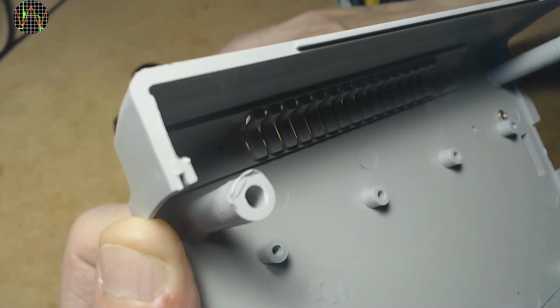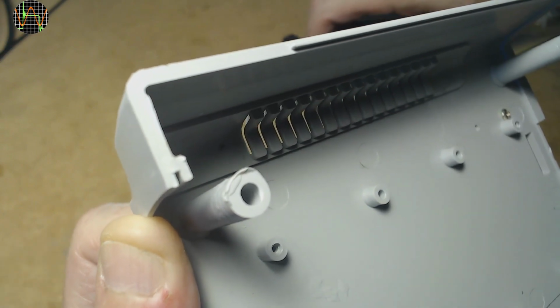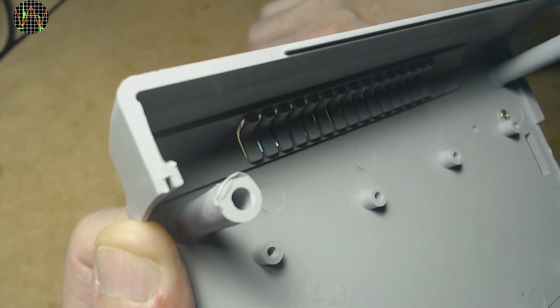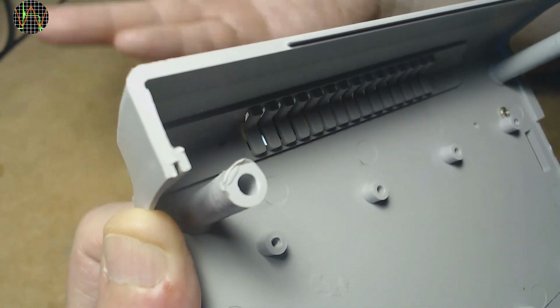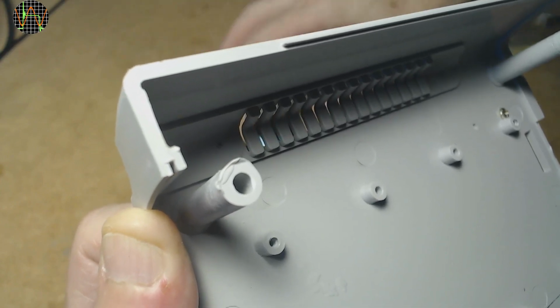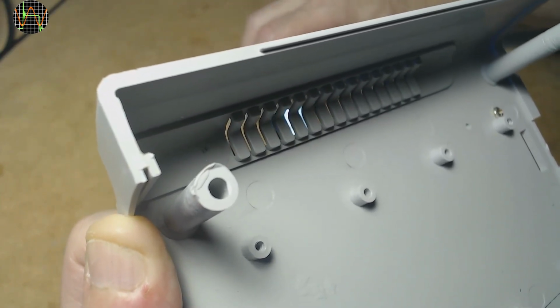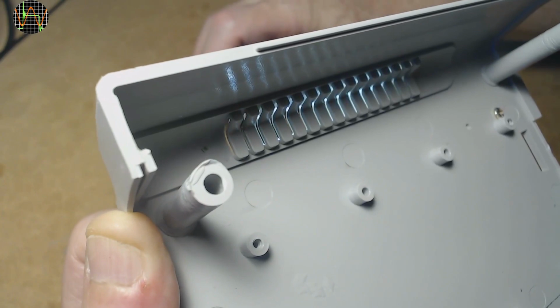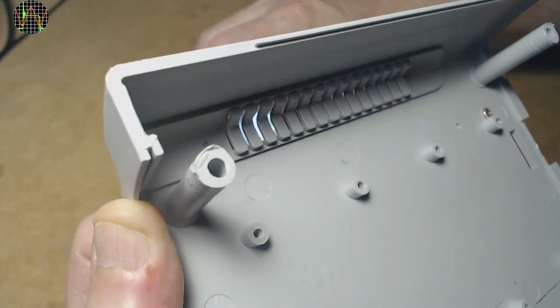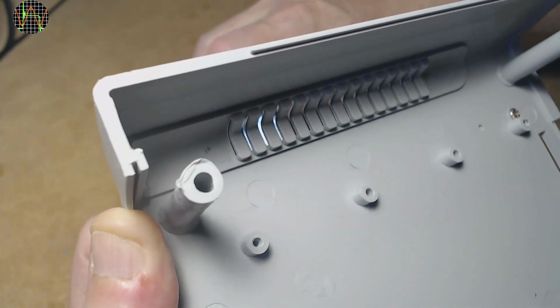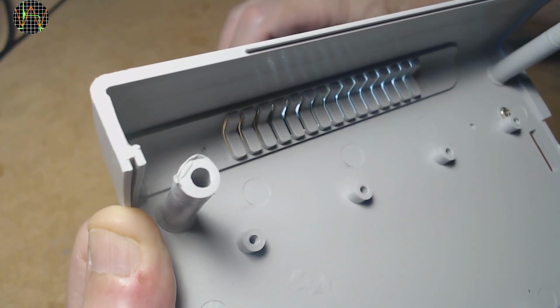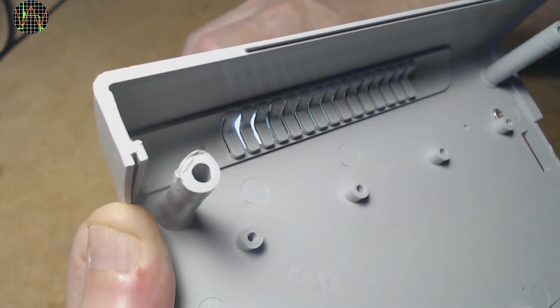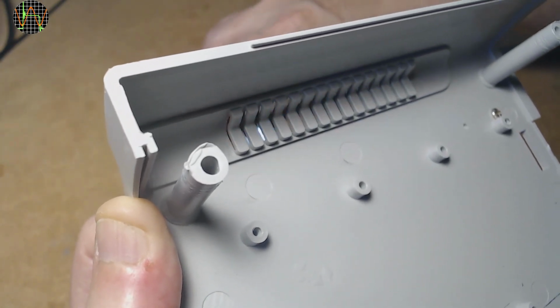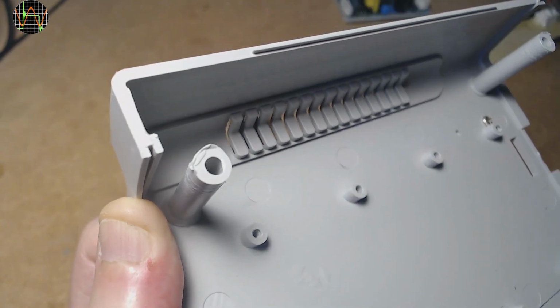The other problem I mentioned in that video is the heat buildup. The housing of the FY6600 has only very few narrow slots at the bottoms of each side and a couple in the rear panel. There's hardly any natural airflow, and if you keep the unit running for an hour, especially under load, you can feel the heat building up inside, which leads to drift in frequency and amplitude.